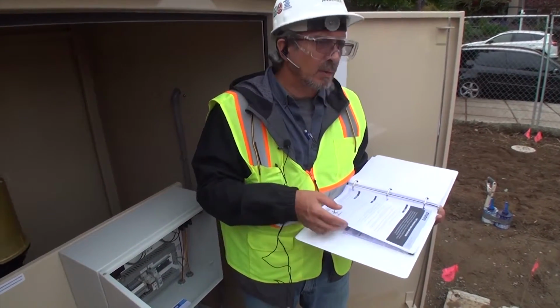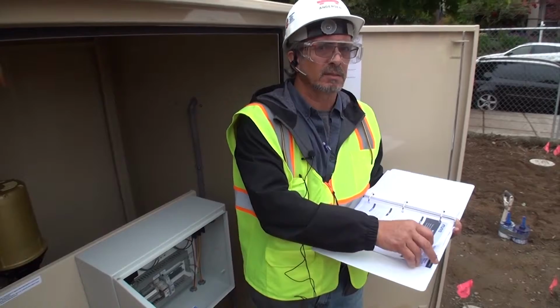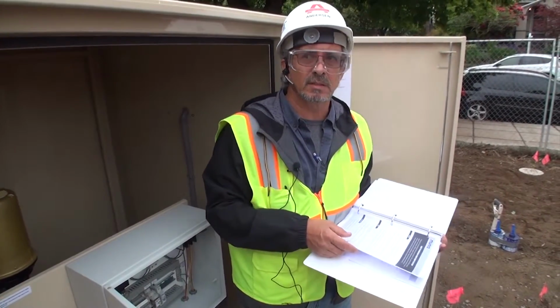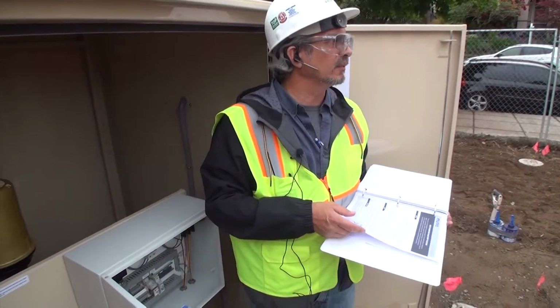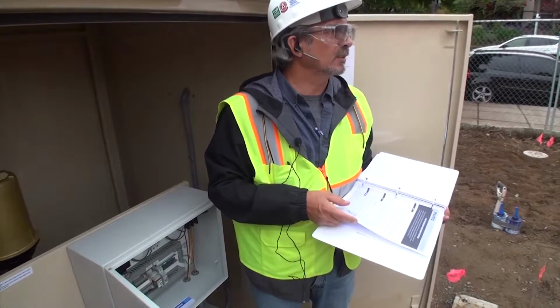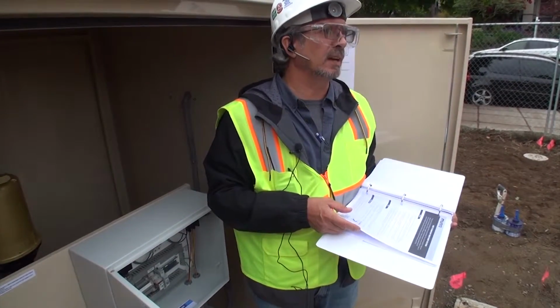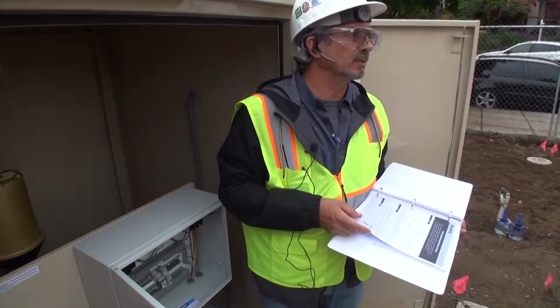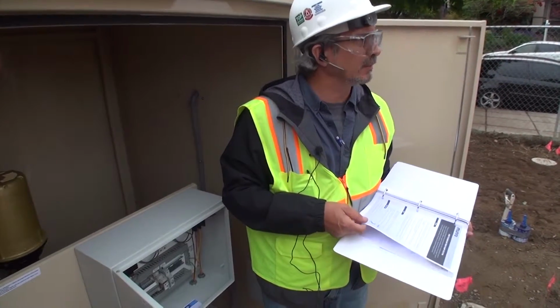What you want to use is type EM grease. EM stands for electric motor grease. There's a lot of greases out there that fit that qualification. You have to check with the grease manufacturer to find out if it's compatible with type EM grease, because that's what the motor manufacturer put in there.